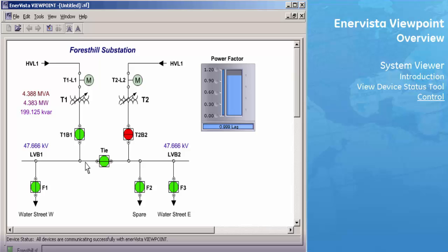Control. In this schema, there are 6 manual indication controlled breakers whose states are manually set in the viewer. There is also 1 automatically controlled breaker whose state changes automatically within the viewer to reflect the value on the device. Finally, there is 1 control breaker whose state is changed on the physical device via commands sent from the system viewer. This state change is also automatically reflected in the viewer. We will now go through the steps on how to utilize these various types of breakers.